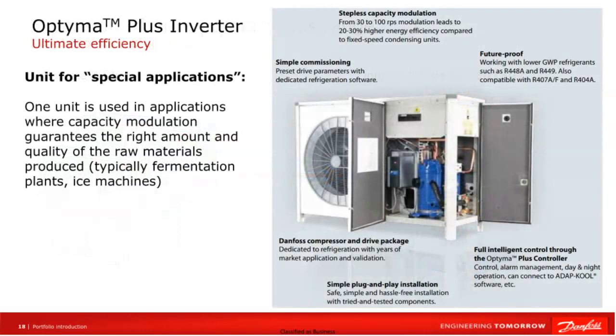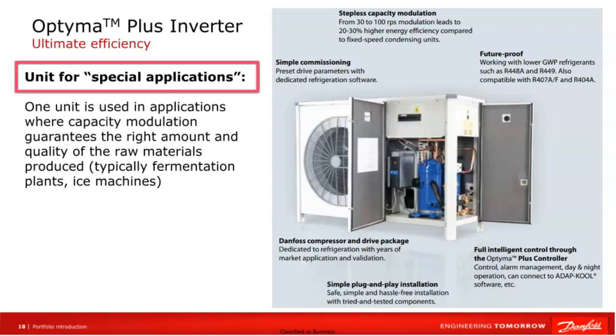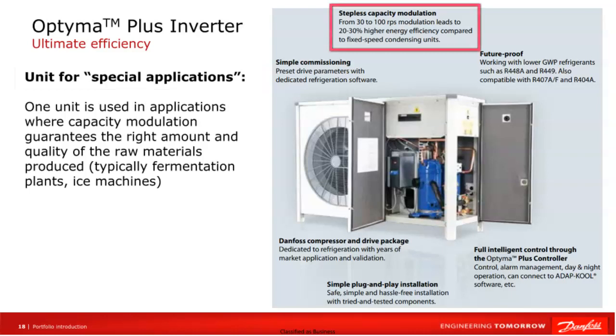As you can see, the Optyma inverter unit can also be referred to as the Optyma Plus version P01 unit. It is a versatile unit that can be called special purpose because one unit is able to precisely adapt to load changes, making it suitable for a variety of applications. For example, in the food industry, in ice machines, in bakeries, etc. Stepless capacity regulation from 30 to 100 RPS transfers into 20 to 30% lower energy consumption compared to fixed capacity condensing units.